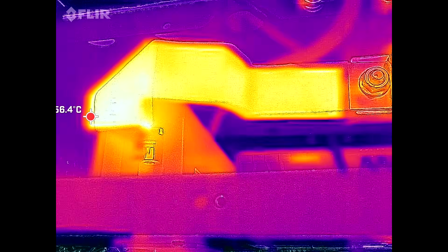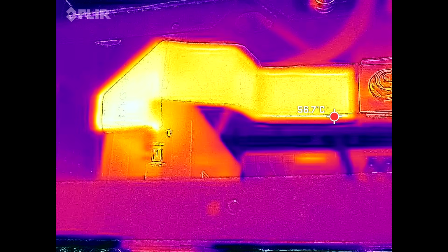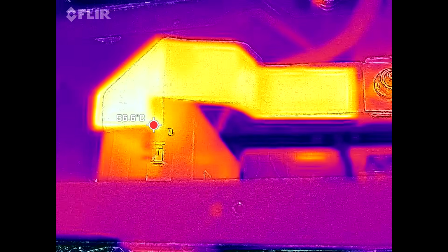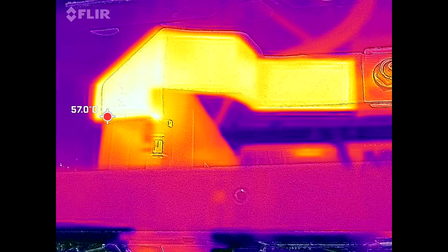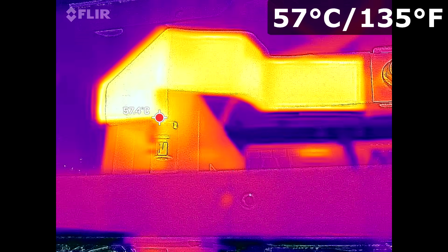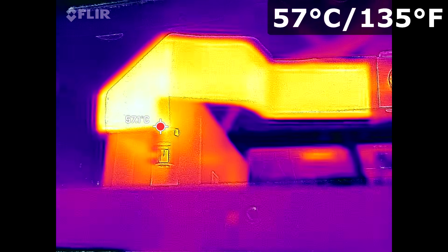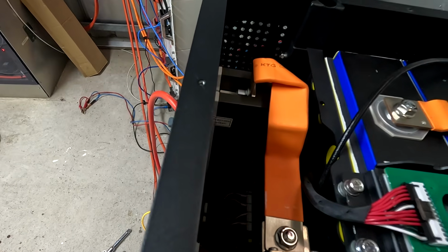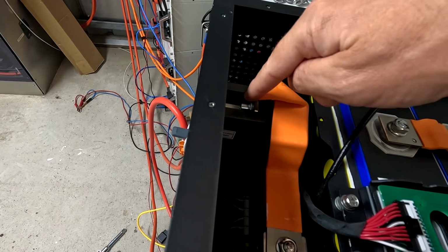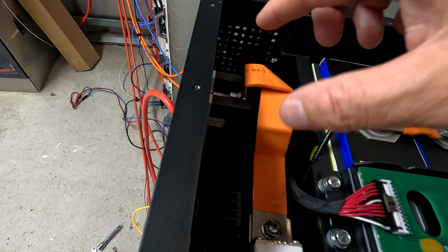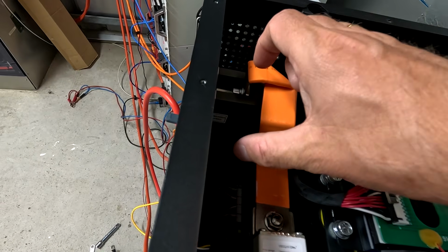So here you can see it again. Yeah, the hotspot is definitely at the connection to the circuit breaker, because the bus bar is smaller in this area and therefore it heats up a lot more than in other areas. So as we can see, the bus bar going into the circuit breaker and coming out of the circuit breaker are actually a hotspot in this section here.